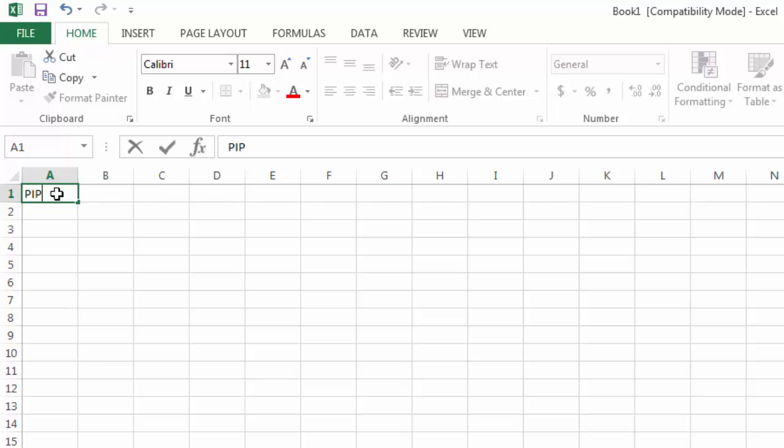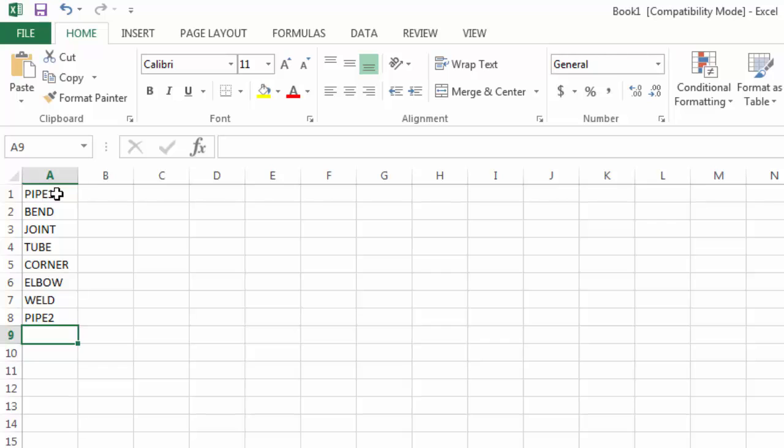I should note there is a 20 character max for the ID number, so you do want to make sure you're under this. You also want to make sure that each ID or TML is unique and there are no duplicates. There should also be no empty rows in the list of IDs, since when GageView Thickness imports the document, it scans the specified column until it hits an empty cell. So you want to make sure there are no spaces or empty cells in the list of IDs.